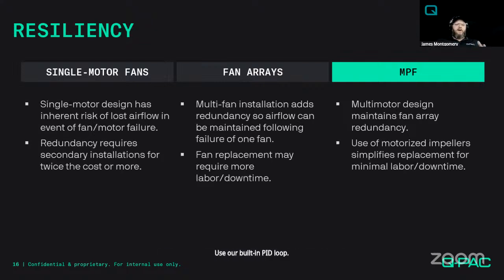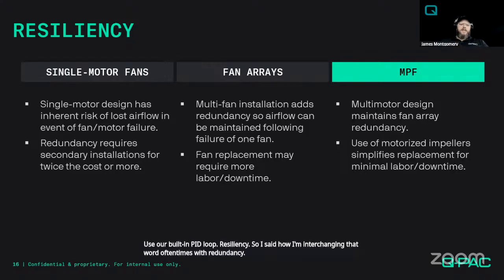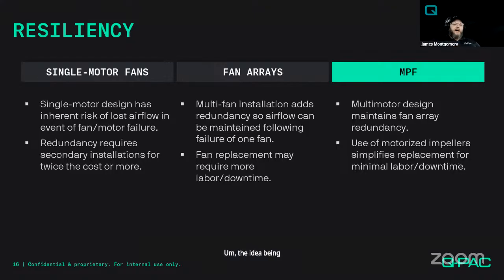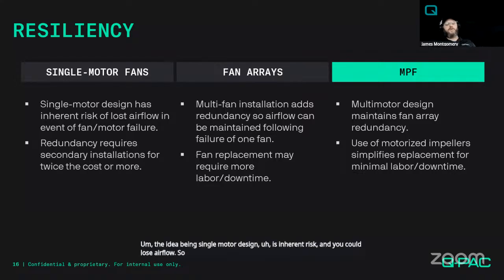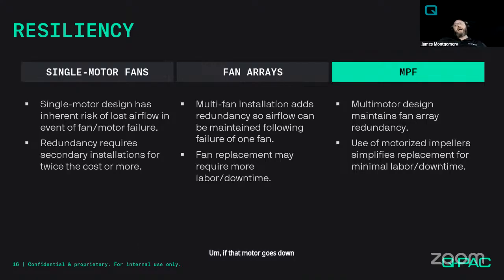Resiliency. So I said how I'm interchanging that word oftentimes with redundancy. The idea being single motor design is inherent risk. You could lose airflow. So in your single motor configuration in those first pictures we saw, if that motor goes down, if you have an issue with that shaft or the belt, if it's belt driven, or if it's just a single blower like with a squirrel cage, if that thing goes down, you're down on air. So the only way you can have any form of redundancy is if you double up. You have two units in the place of one.